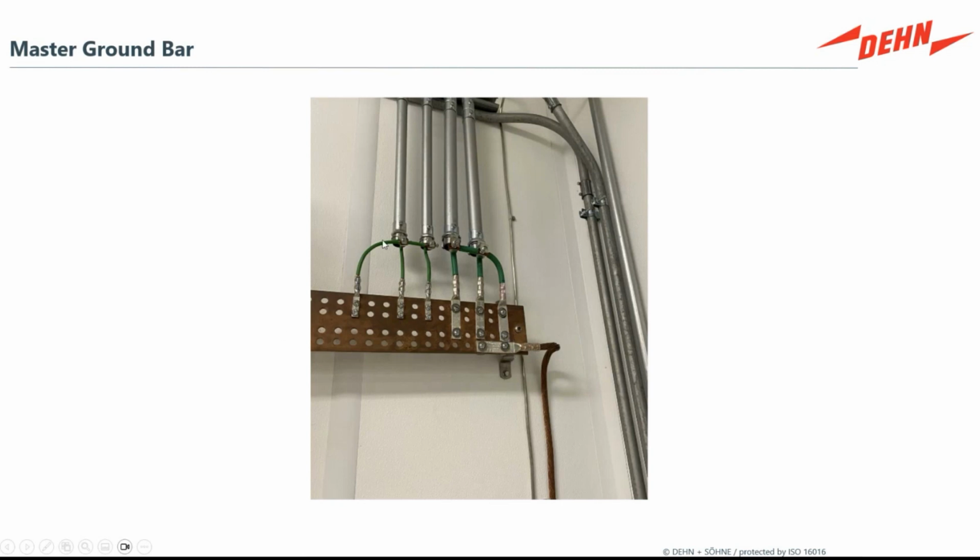There's a couple things I like personally about an image like this, things like the two-hole lugs that prevent them rotating and coming loose over time quite as easily. Things like the conduit, you have clear conduit connections, and all the metal components are also bonded in with your grounding system. So these are just a few images that we look for and that are important.